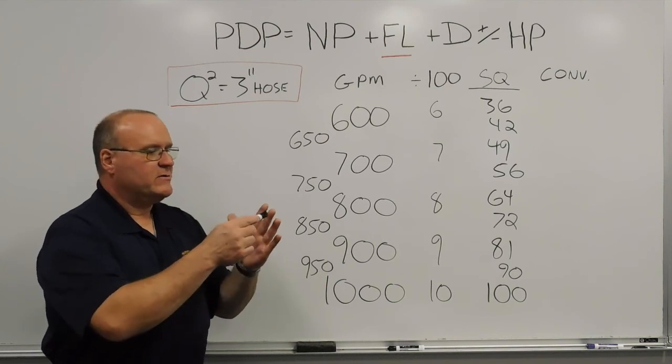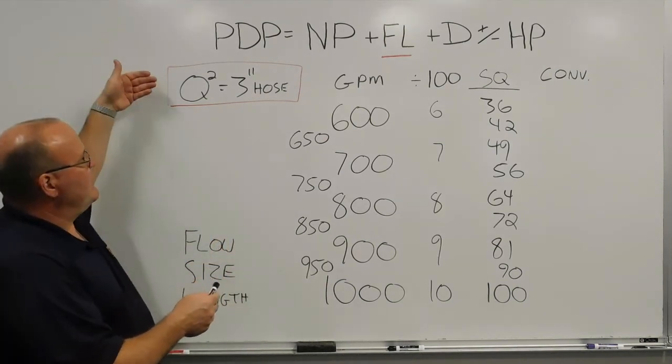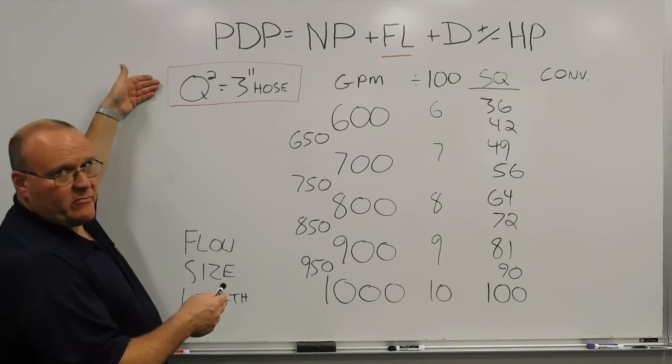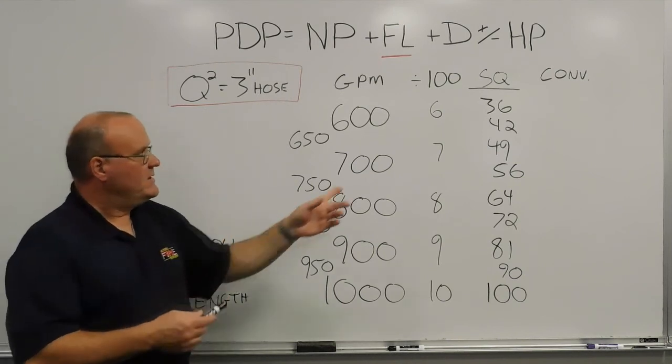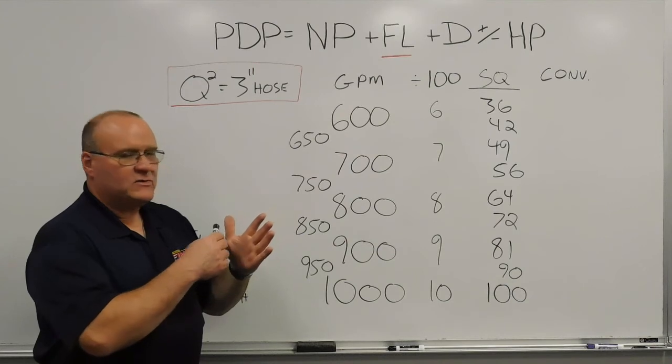you'd have 100, 200, 300, 400, 500 and to get to a 3 inch friction loss number for every 100 feet, you would simply divide by 100 and then square that number.